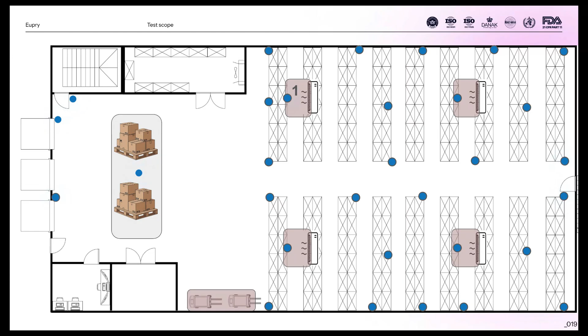In terms of things to test during the mapping, the key points are, as Alex mentioned, you should identify the risks and the underlying risks. We always recommend following the rules of thumb, the guidelines. But basically, the major ones are that the temperature is homogeneous, so it's the same to a certain degree all around, that it's stable and doesn't vary up and down too much during the exercise, and that it can handle the operational usage. So if you have a warehouse and you open and close the doors, you will do that during normal operation, hopefully—otherwise it's a pretty useless warehouse. So it should be able to handle those external influences, both during summer and winter, and that's really what you want to show. We should also ensure there are no positions that experience out-of-scope temperatures. It's really hard to find specific points, but those are the top ones.